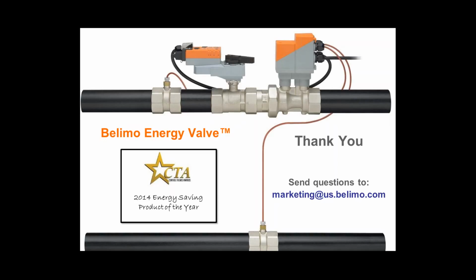Okay. And this question I'm not extremely familiar with. It says, I have a primary pump set with 150 TR chiller. I get more than 5 delta T. Any suggestions? I'm assuming what he's saying is that he has a variable primary chiller set up and he has a low delta T. If that's the case, the energy valve delta T strategy works well on variable primary or primary secondary pumping strategies. And again, what we're trying to do is just force the building or buildings, depending on if you're a campus or what have you, to utilize less water.